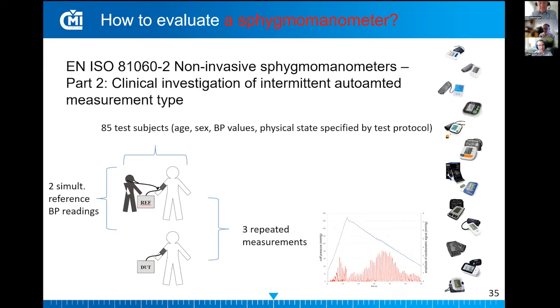The procedure is based on the European standard 81060-2, clinical investigation of automated sphygmomanometers. It is based on quite simple assumptions: if we test the sphygmomanometer with a large enough sample of 85 test subjects, divided according to age, sex and blood pressure values, without any significant obstacles for blood pressure measurements, with several repeated measurements, then we could obtain a quantitative and qualitative description of the tested devices.